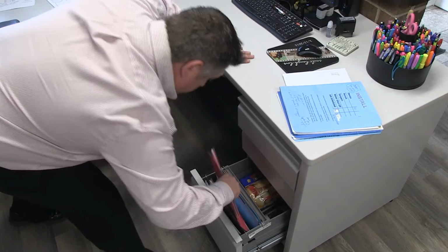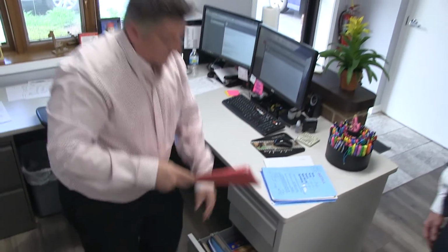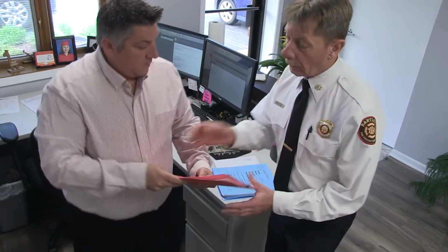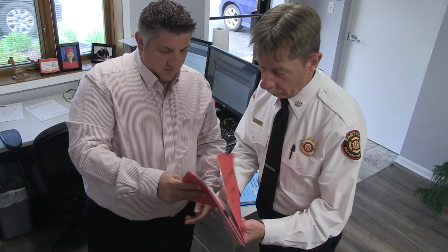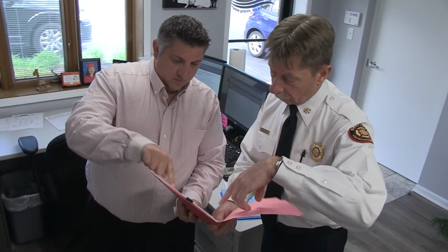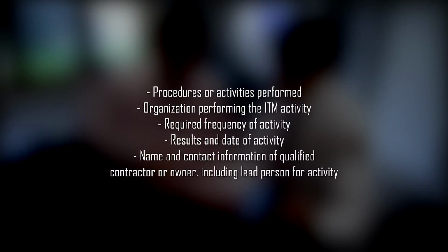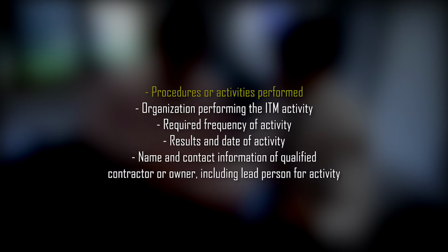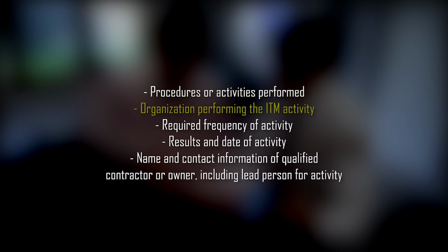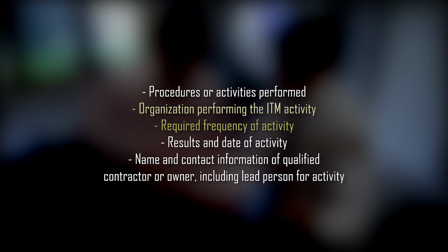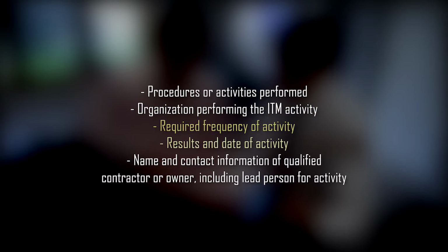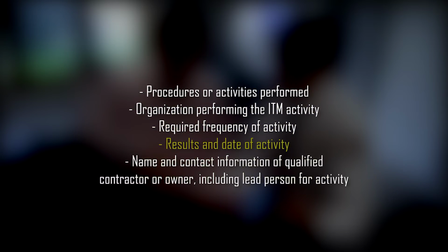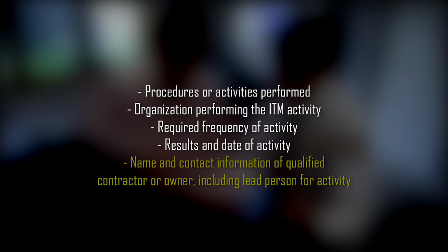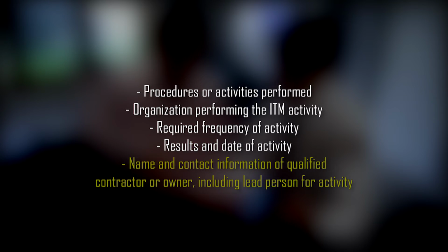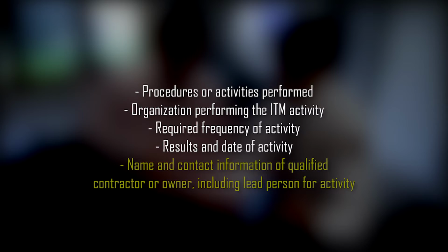You, as the building owner or manager, are responsible for maintaining all records for ITM of your system, so they can be made available to your local authority having jurisdiction upon request. Your record should indicate the following: procedures or activities performed, the organization that performed the activity, the required frequency of the activity, the results and date of the activity, and the name and contact information of the qualified contractor or owner, including the lead person for the activity.